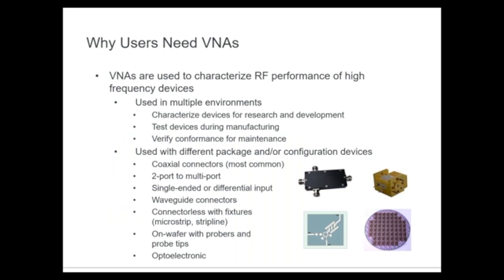The VNA is really best thought of as a stimulus-response instrument. It generates its own test signal, applies it to the device, and then measures various signals coming back — both signals transmitted through the device as well as reflected from either interface. So we're typically looking at transmission and reflection characteristics, which we then translate into S-parameters.